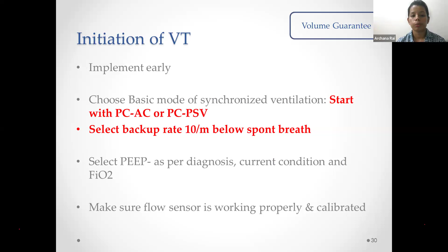Usually the targeted expired tidal volume is set between 4 to 6 ml per kg, and the pressure limit is set, and the ventilator will adjust the working pressure. Once we know the working pressure, we should again reset the PIP limit to 3 to 5 centimeters of water, that is 30 to 50% above the working pressure. And we should always use the proximal flow sensor.